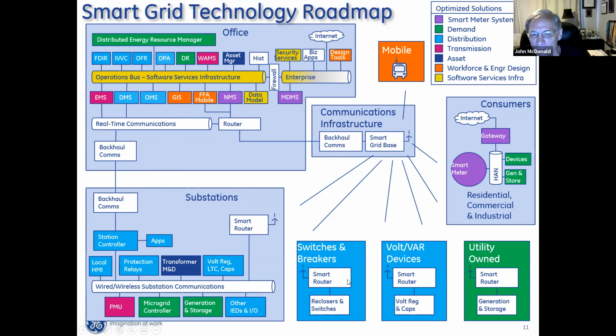And then the equipment here on the feeders, the switches and breakers and the volt var devices, those support the logic. The switches and breakers support the FDIR logic, fault detection, isolation, restoration. And the volt var devices, these are capacitor banks and voltage regulators, support the integrated volt var control logic. Now that logic can be running at the control center or at the substation level, okay?